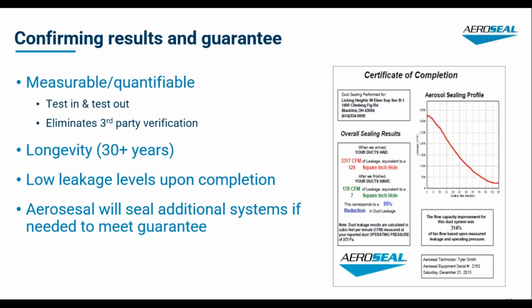So how we confirm those results: this is our certificate of completion. Every time we do a section of ductwork, we're telling you how much leakage is there when we started sealing and how much leakage is there when we're done. We compile all of those together for each building or system, and we find what percentage of leakage was there and what percentage we sealed up. Those inputs go back into those energy models. So this is something that eliminates any other verification. We tell you what we're going to do, and then we have data that we did it.